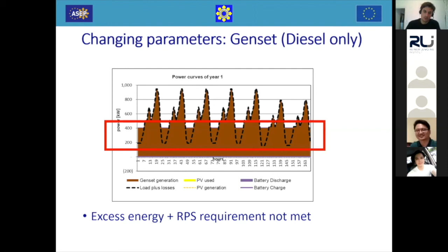And you don't have to do this now, but I will just show what happens if we choose 5 plus generators, or if you use more generators as we did before. Of course important is that we choose also as a smallest generator unit a low kilowatt peak. So for example, now we have 250 kilowatt as the lowest capacity of a generator. And this smallest generator can adapt to the low load. And therefore no excess generation is produced because the larger generators stay idle.